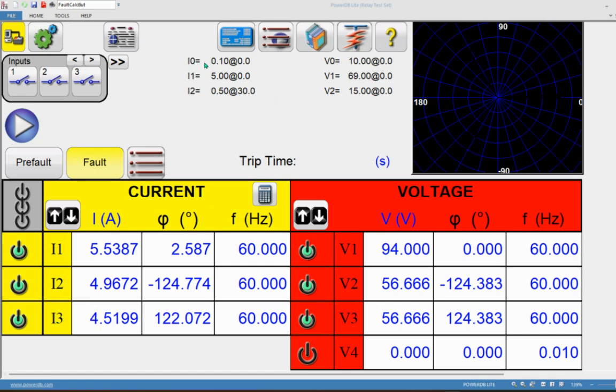The display at the top confirms what is being injected. Even though IA, IB, IC show different values, the fault calculator automatically populates the actual I1, I2, I3 values based on the entered data. Similarly for voltage: V0 was 10, V1 is 69, V2 is 15 volts. This tool is really handy when testing motor protection relays — for example when you want to inject a certain level of negative sequence, positive sequence, or zero sequence.